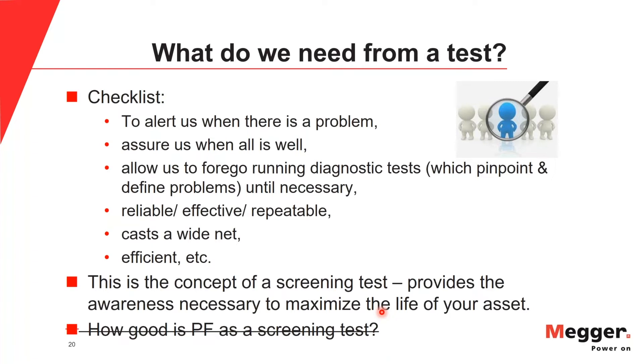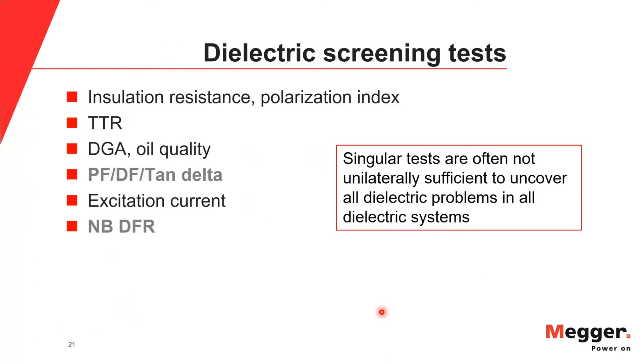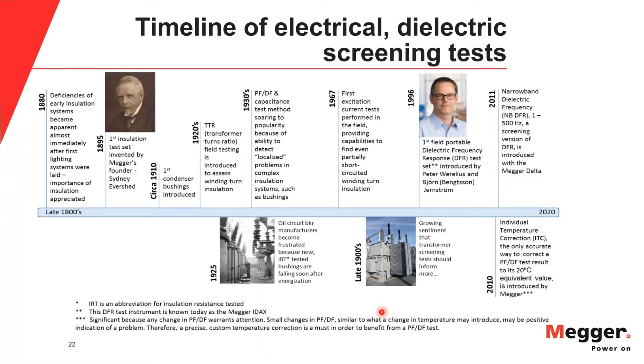It would be tempting to ask how good power factor is as a screening test, but we haven't properly introduced it yet. How many screening tests exist to test insulation in a transformer? Here is the list given in order of when each test was introduced for use on transformers. A single test is really not sufficient to screen for all dielectric problems in a transformer. On this timeline of electrical screening tests, insulation resistance and polarization index testing came first, followed by TTR testing in the 1920s. DGA and oil quality tests are included as well.